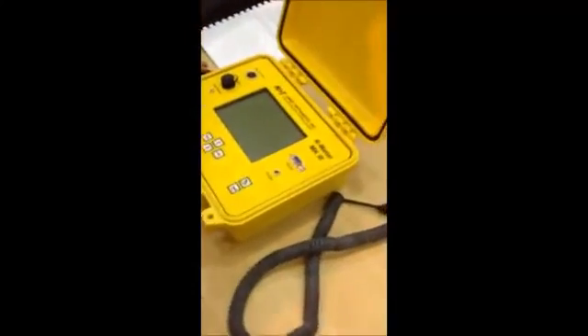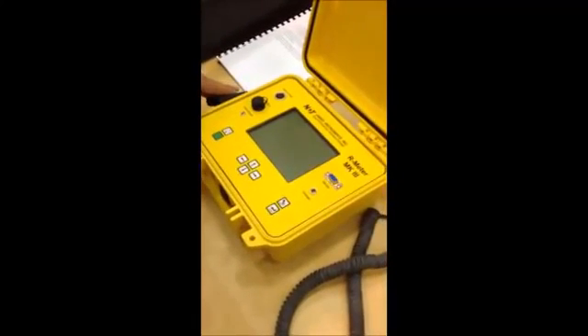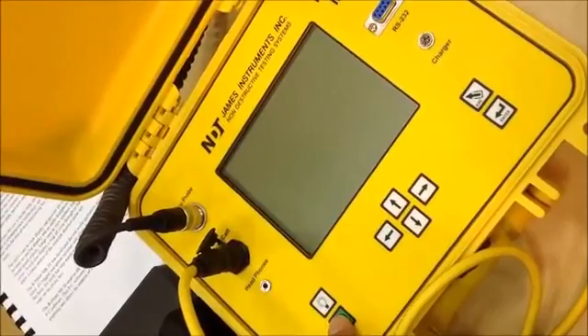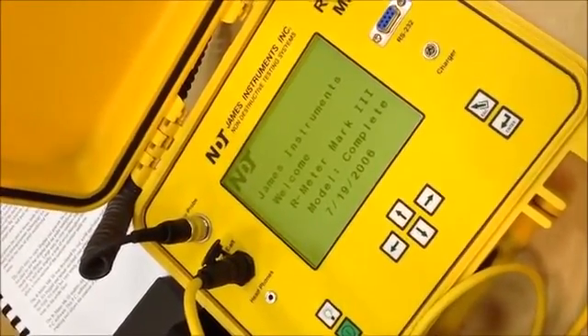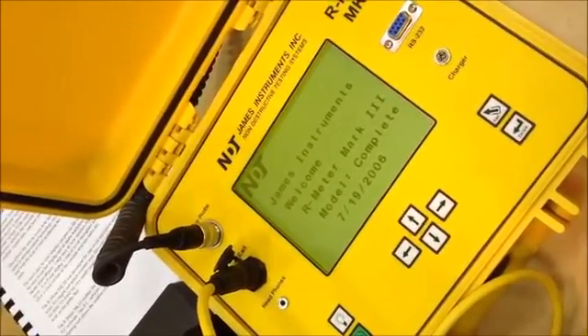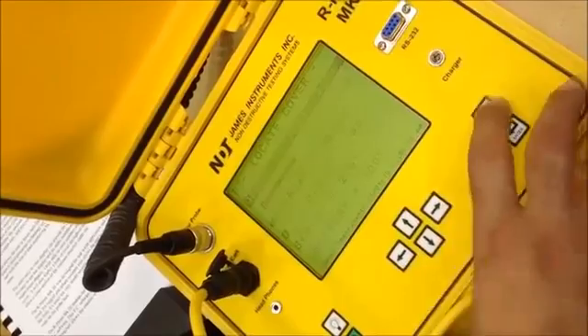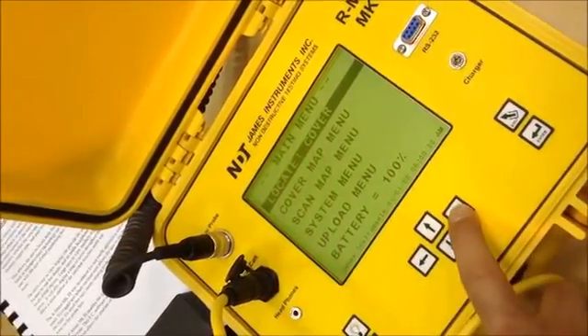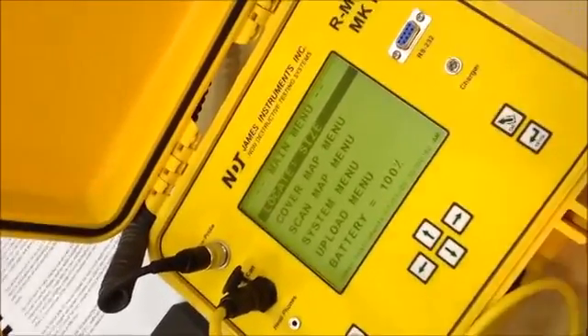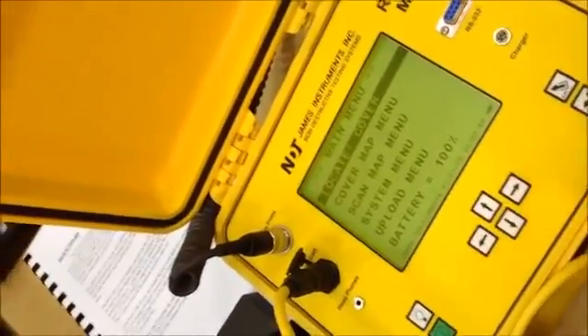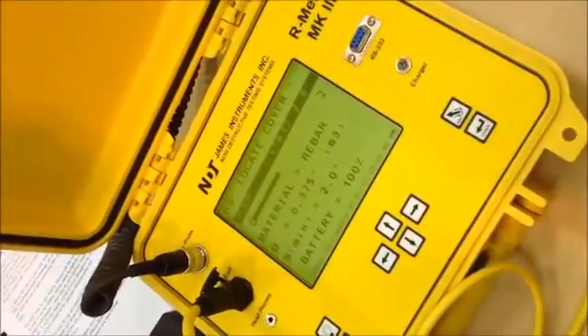Today we're going to talk about this instrument, R meter MK3. It determines the depth and estimate the size of the metal objects inside the concrete. And now we're going to start connecting it. After we finish connecting it, now we're going to start setting the device. Now we're going to turn on the device, and by default it's going to start estimating the cover. But we can just go back, and either we can start the cover and the size of the steel. But now we are going to choose the cover, and we're going to test it now.